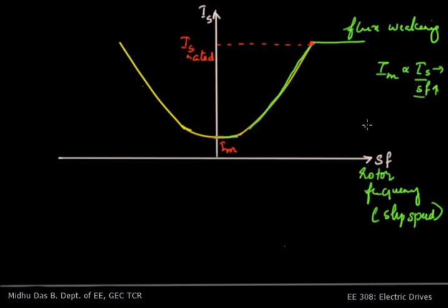Then at base speed, slip is low, the machine will reach its rated machine voltage, or the variable frequency current source voltage will saturate. So in either case, the machine operates at a constant terminal voltage above the base speed. Therefore, it will go to constant power mode above the base speed. The performance is similar to a variable frequency voltage source inverter drive. So the variable frequency for the current supply here is provided using a current source inverter.